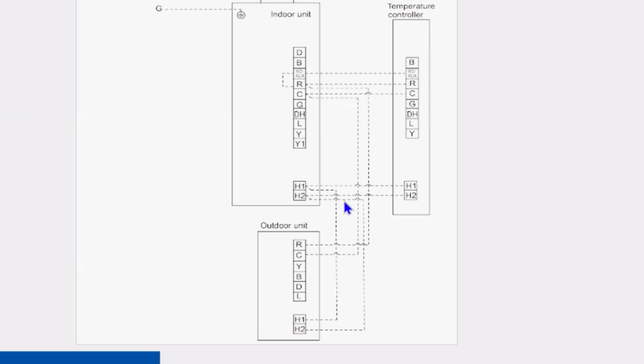Now, it's pretty simple to do, and I can show you again at the air handler. They actually give you multiple connections, so it's real easy to make your connections from the outdoor unit. You're going to have a set of separate screws that you can screw on to get on the H1 and H2 here. Then you got another separate set of screws for H1 and H2 that'll allow you to hook up the controller. So it makes it really convenient. You don't need a bunch of wire nuts and stuff like that. So it's not hard to do at all.